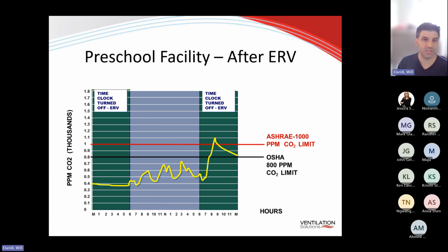The reason why there's that spike over here is that the equipment is probably turned off once the school goes into unoccupied mode, basically. So if there's any maintenance people in the space, or if there's parent-teacher night or whatever, sometimes it would spike up to that level. But regular occupied hours, that's where it matters the most. That's where most people would be occupying that time frame.